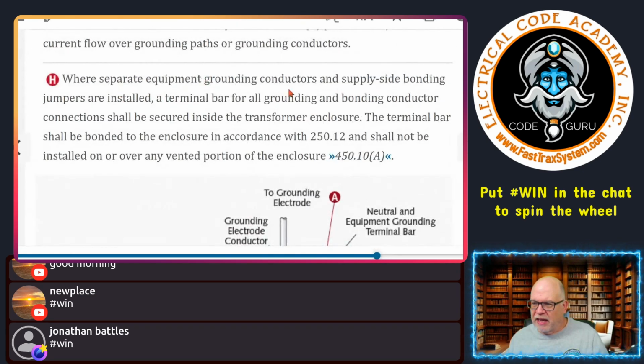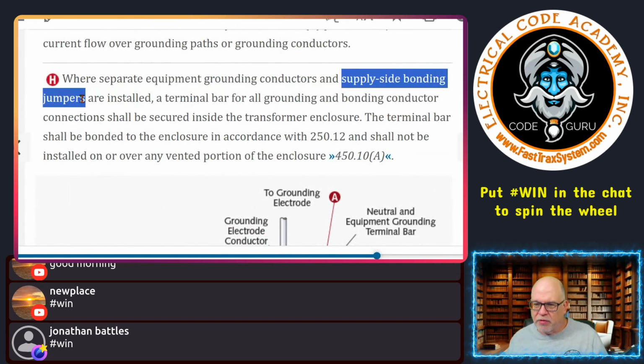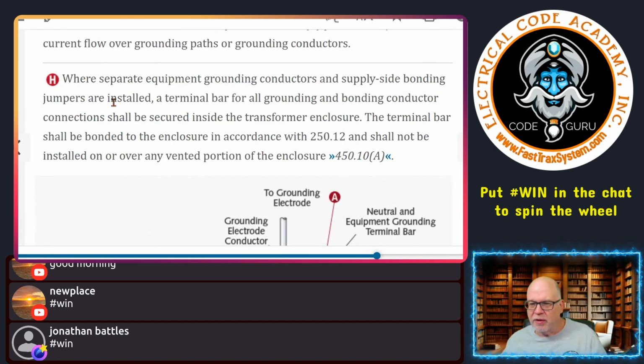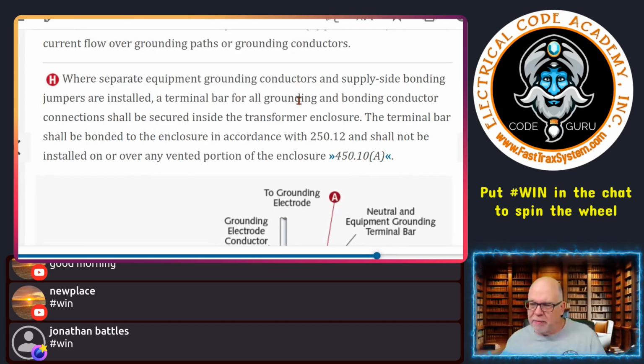equipment grounding conductors and supply side bonding jumpers, which is what we talked about, that's going up to the first disconnecting means, are installed, it says a terminal bar for all grounding and bonding conductor connections shall be secured inside the transformer enclosure. The terminal bars shall be bonded to the enclosure in accordance with 250.12 and shall not be installed on or over any vented portions of the enclosure. That's in 450.10(A). Remember, folks, we give you these chevrons for a reason.